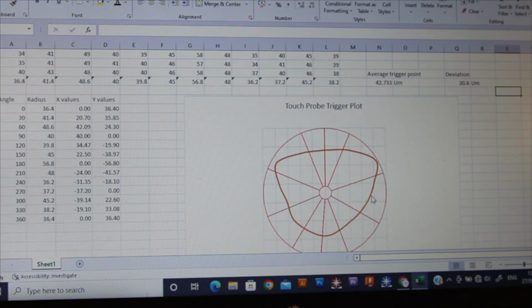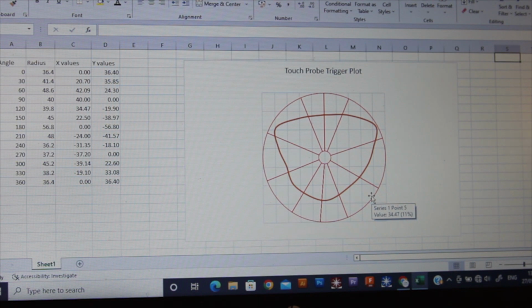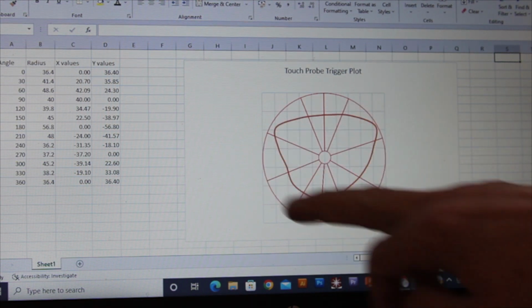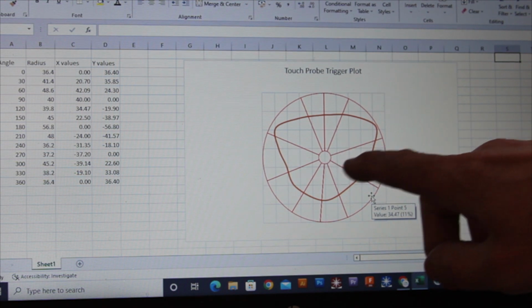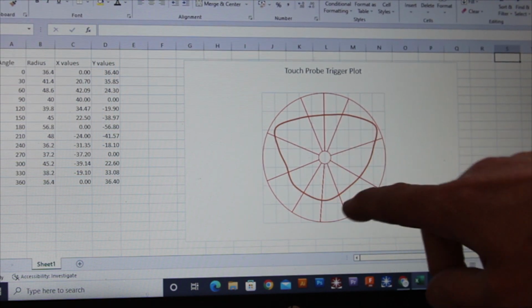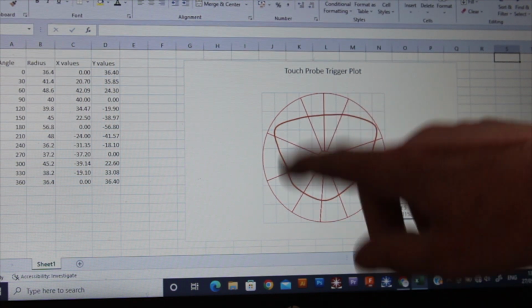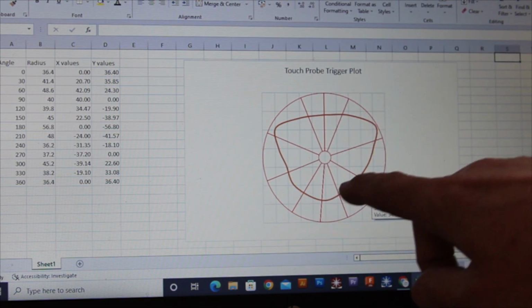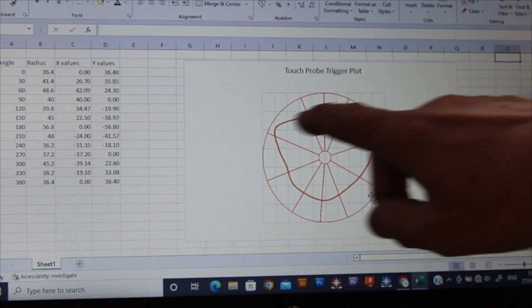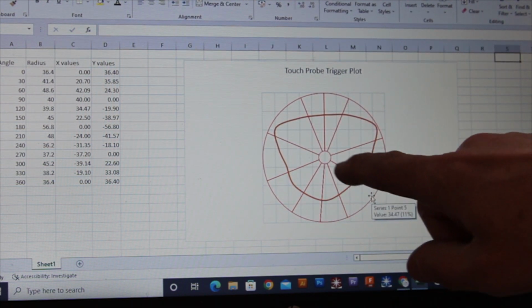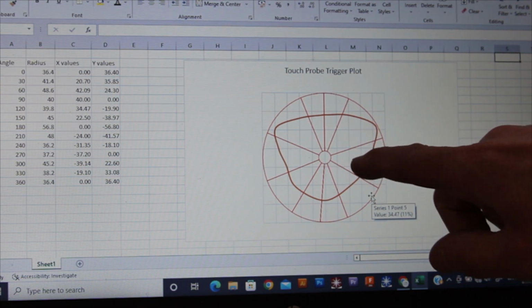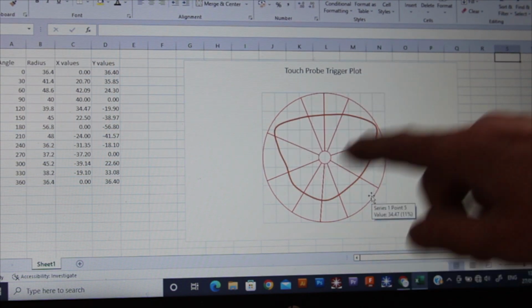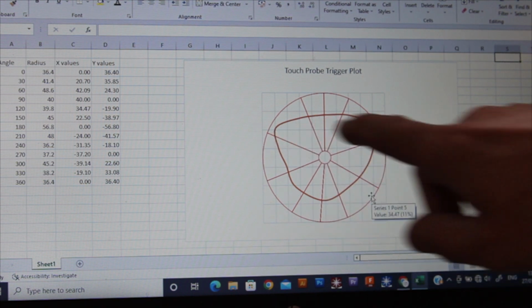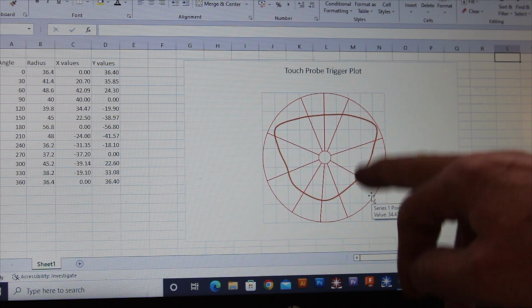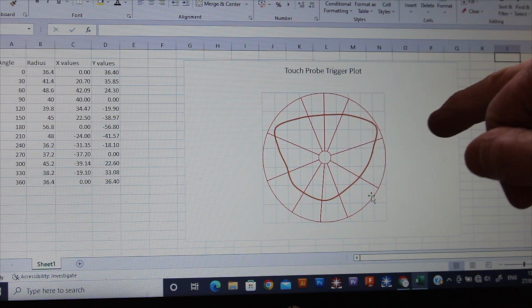So it's pretty accurate. And if we look, after a great deal of messing around because I'm not very good at Excel, I've done a polar plot of how accurate it is, or when it triggers. The closer this is to a circle, the better. But as you can see, there's roughly 3 lobes, and that is down to the fact that the kinematic probe system has 3 touch points. You can see they're roughly 120 degrees apart. So that is, I think, a relatively typical response for this type of probe.